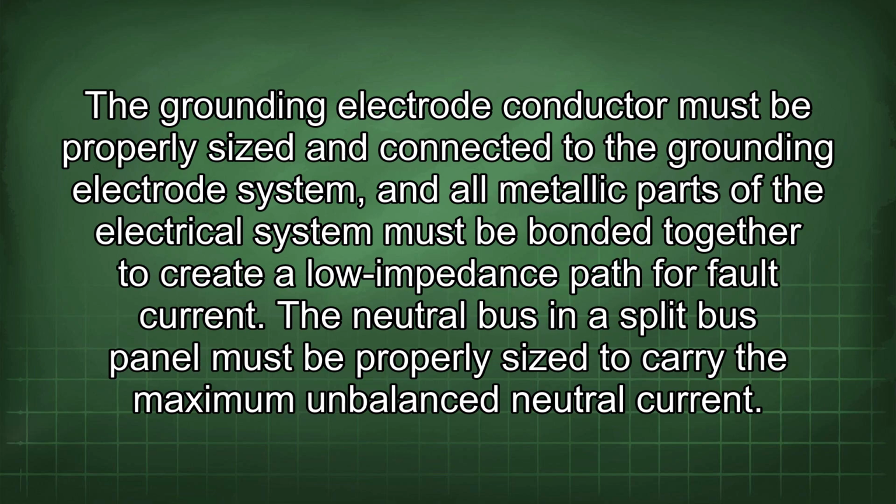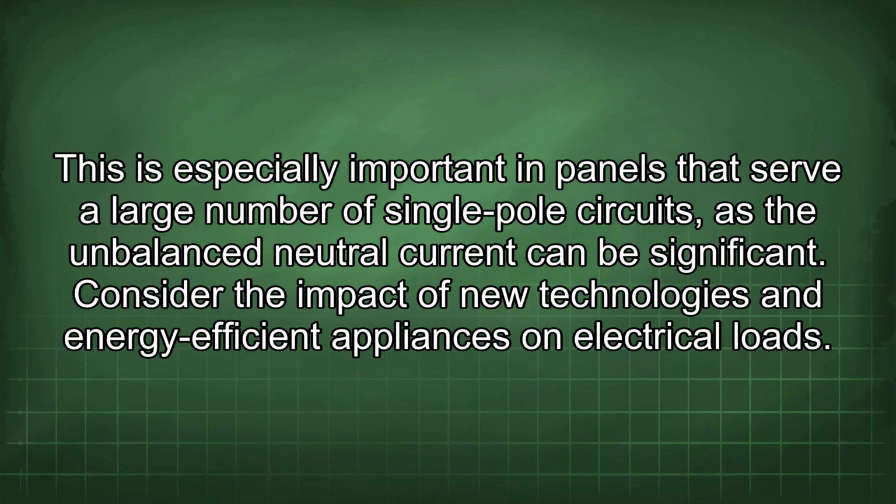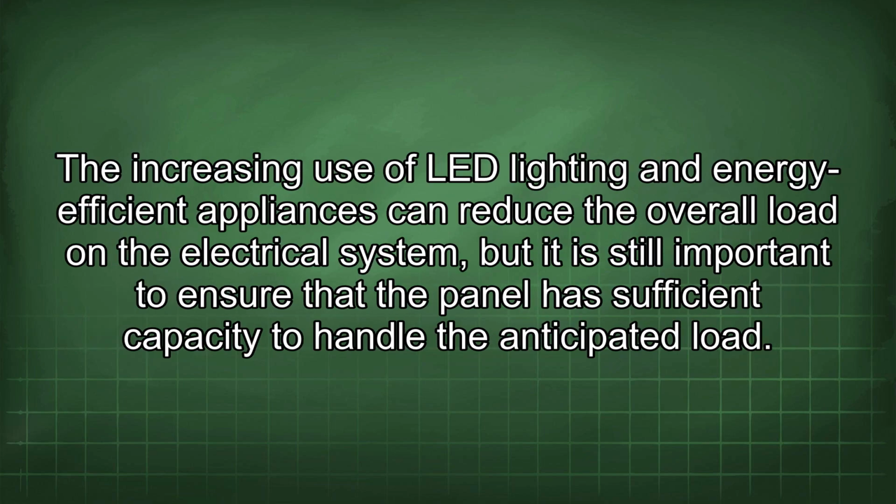The neutral bus in a split bus panel must be properly sized to carry the maximum unbalanced neutral current. This is especially important in panels that serve a large number of single-pole circuits, as the imbalanced neutral current can be significant. Consider the impact of new technologies and energy-efficient appliances on electrical loads. The increasing use of LED lighting and energy-efficient appliances can reduce the overall load in the electrical system, but it is still important to ensure that the panel has sufficient capacity to handle the anticipated load.